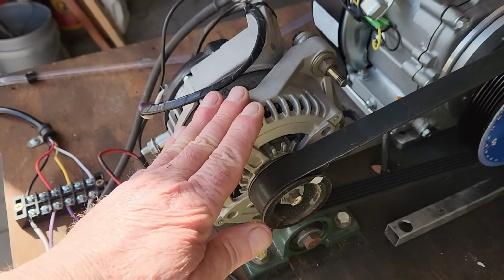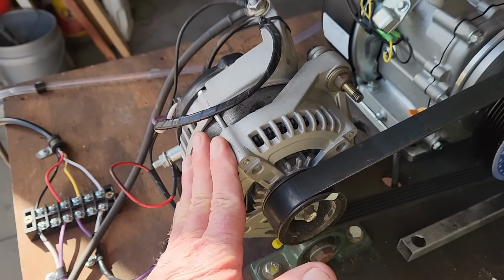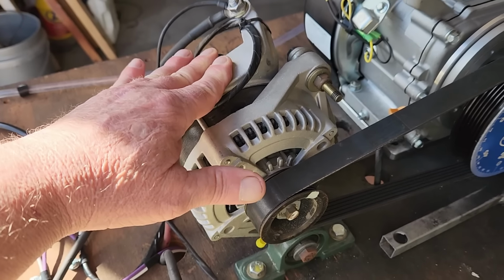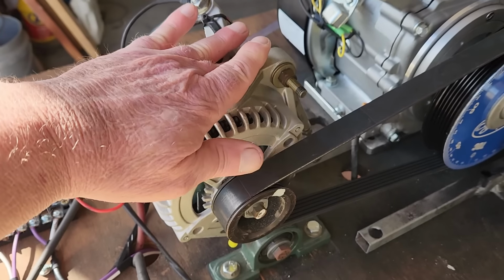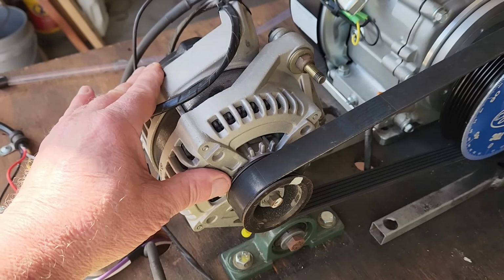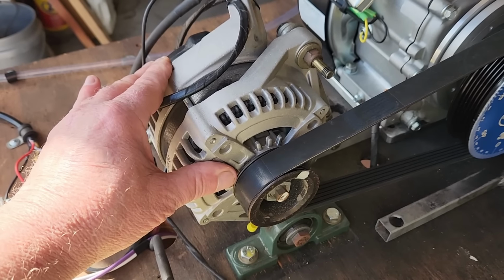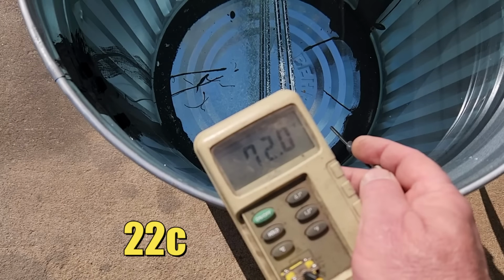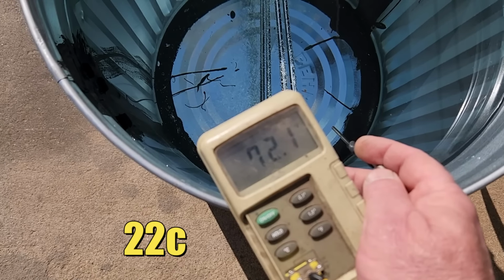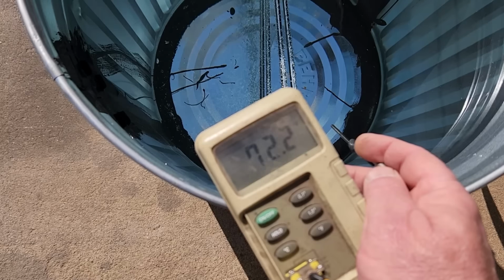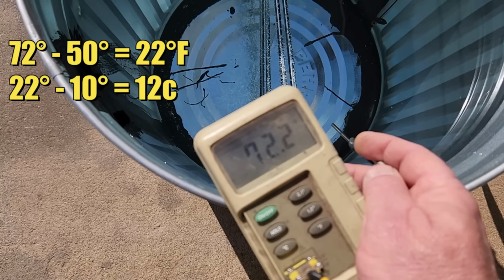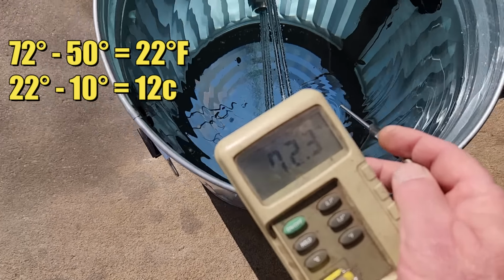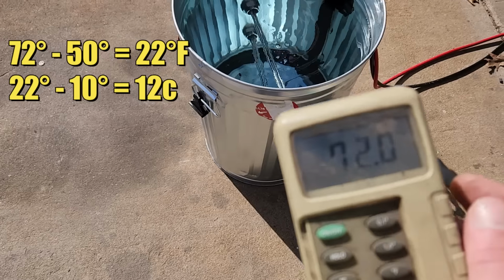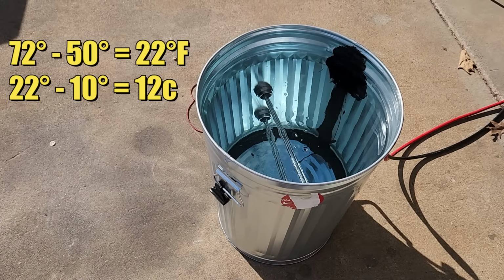Well, the alternator is hot, but not too hot. I suspect this is about normal hot, if that makes sense. There were no weird smells, and I have no problem touching the case of the alternator, so I'll call this a win. The trash can full of water is measuring 72 degrees Fahrenheit, so we started at 50 degrees and raised the temperature by 22 degrees over 45 minutes. Basically, we were running the system at half power.